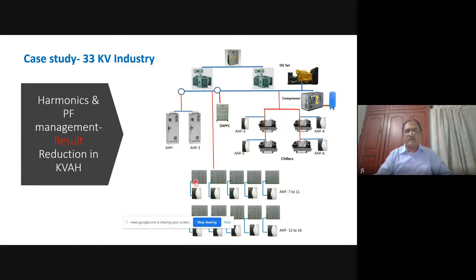Each MCC had multiple outgoing, and each MCC was addressing a group of machineries. So 10 sets of machineries were being managed by 10 MCCs. When we did the analysis, we found out that the damage was being caused by a circulating voltage harmonic, which was caused by a leading current harmonic. So we put an active harmonic filter for each of the MCCs at the incomer, preventing a rise in current harmonic and also distribution of voltage harmonic to the parallel branch circuit.